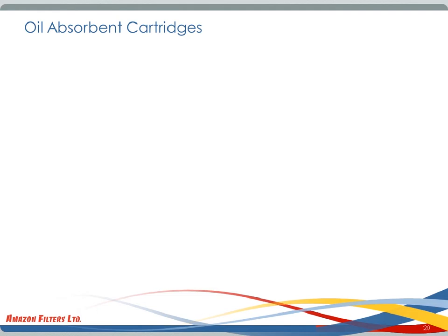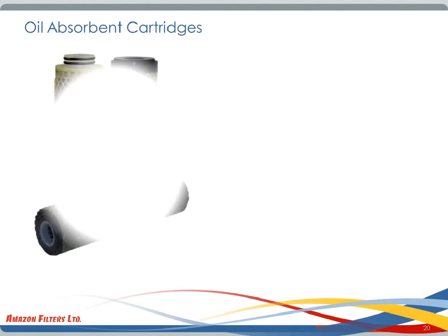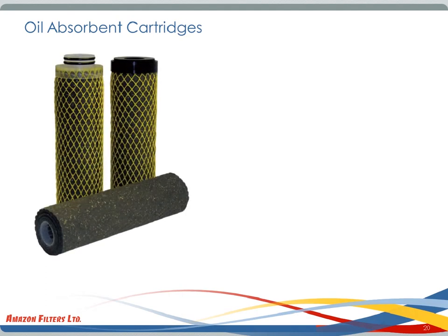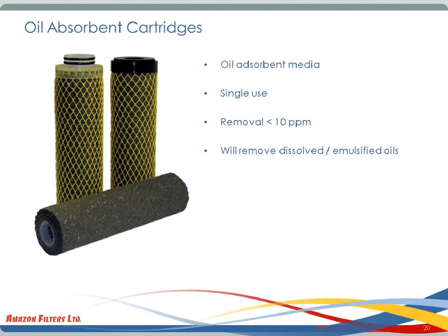Oil adsorbent cartridges are also used as a tertiary stage. These operate on the same principle as the nutshell filter. However, they cannot be regenerated, therefore they are a single-use disposable technology. These have many of the advantages of a cartridge filter for solids removal in terms of low capex, a compact footprint and weight, and an insensitivity to process upsets.